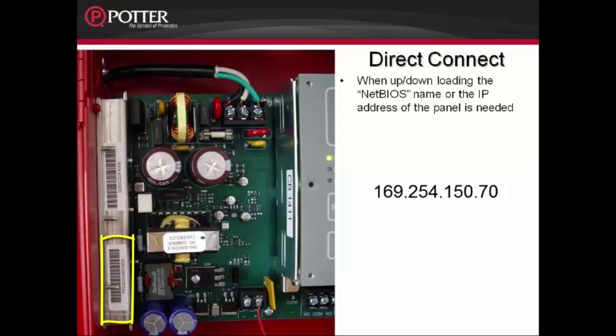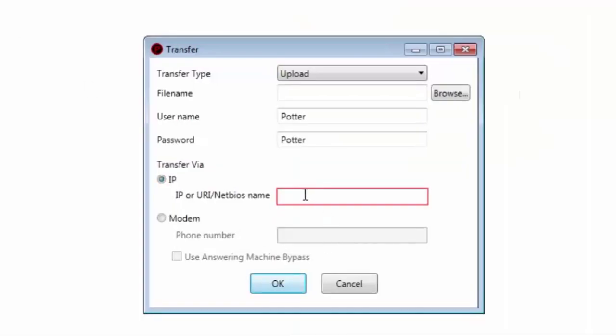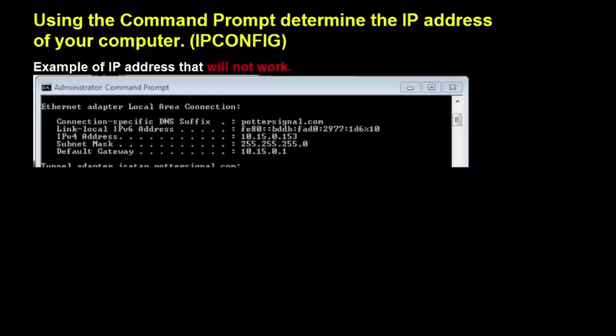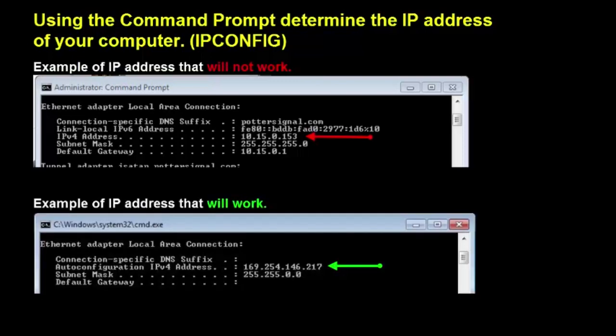The NetBIOS can be found on a sticker inside the Fire Alarm Control Panel on this heatsink as you can see here. The first time you try and communicate with the Fire Alarm Control Panel, it is recommended that you use the IP address. You also want to make sure that the IP address of the computer is similar to the IP address of the Fire Alarm Control Panel. For example, if the IP address of your computer is 10.15.0.153, it is not going to communicate with the Fire Alarm Control Panel that is a 169.254.150.70. For information on finding out the IP address of your computer, as well as changing the IP address of your computer, please refer to the IP Troubleshooting Tools video.